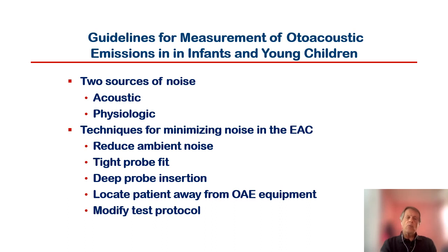Now, in recording OAEs from children, one of the challenges is we need to make sure that there's very little noise in the ear canal. Remember, the OAE is actually a sound that we're recording, a very low intensity sound in the ear canal. So any background noise, ambient noise from the room, the test room, acoustic noise, or physiologically produced noise, breathing, moving, can all obliterate our detection of, or prevent the detection of the OAE.